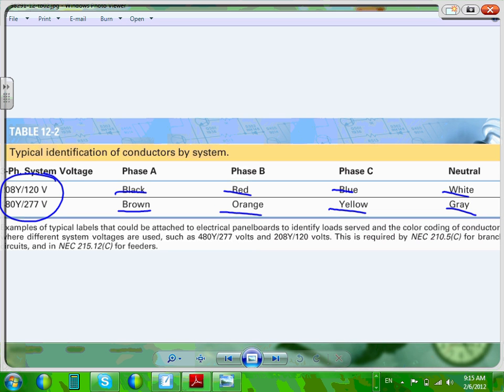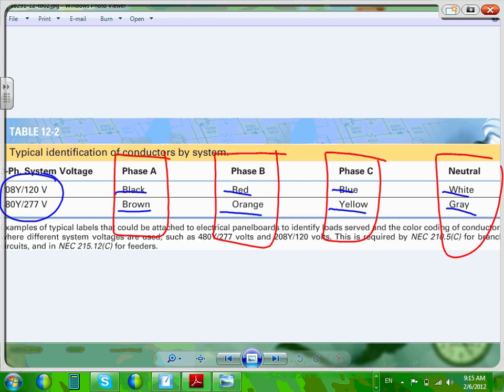Okay. This is a major thing. Number one. Number two, also, Ashley, if you have two systems like us at Dunwoody, we have multiple systems, 208, 120, 480, 277, then also the conductors have to be color-coded. You have to color code them. Can you see the phase by phase? Everybody can see how they're color coded by phase and by neutral. Can you see how every phase of every system is different? By phase and by system.